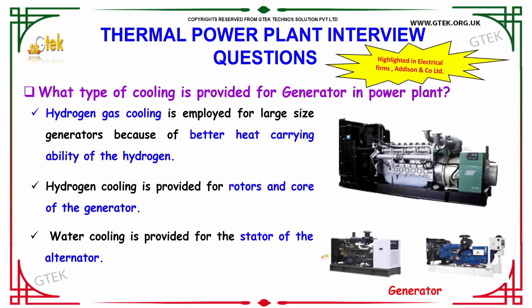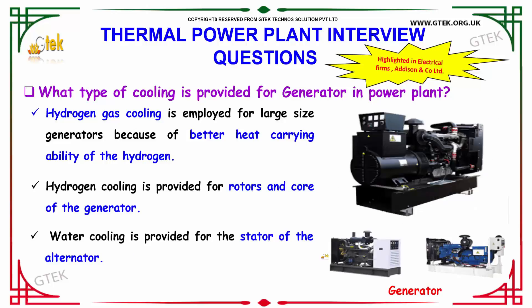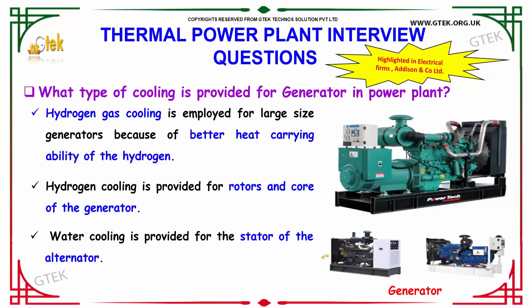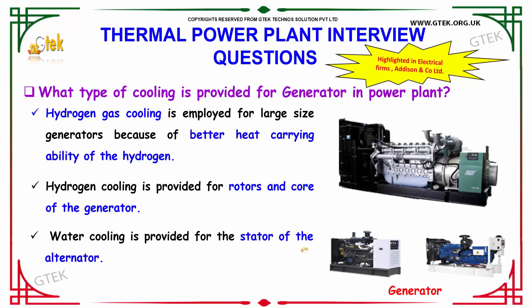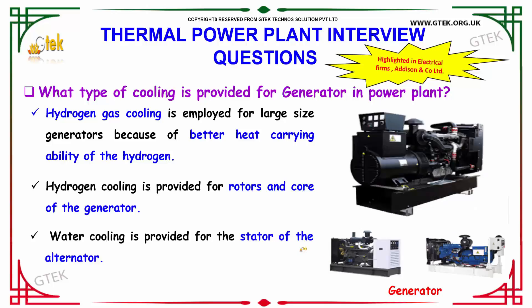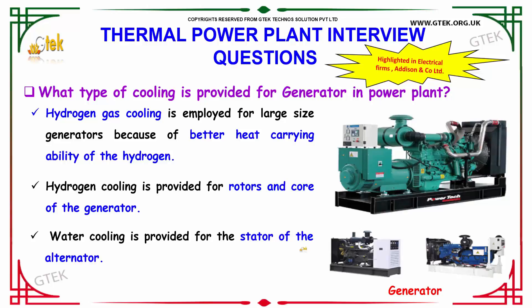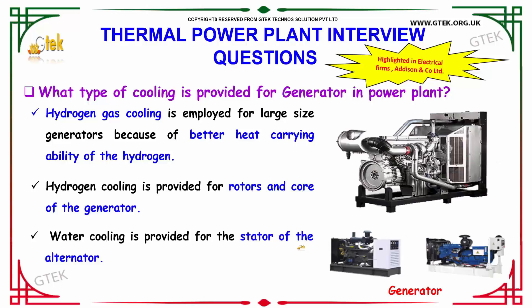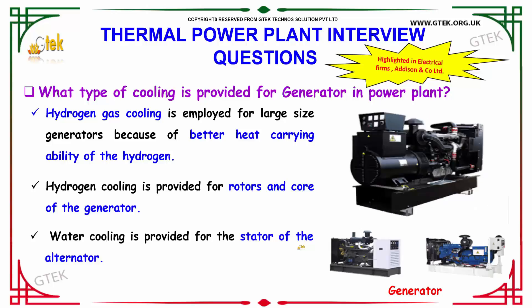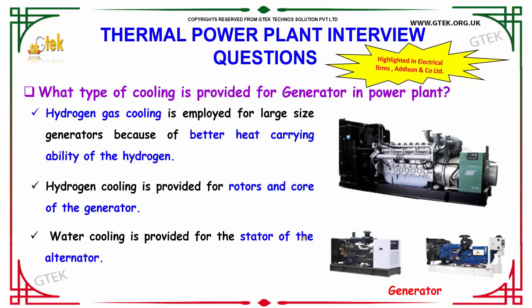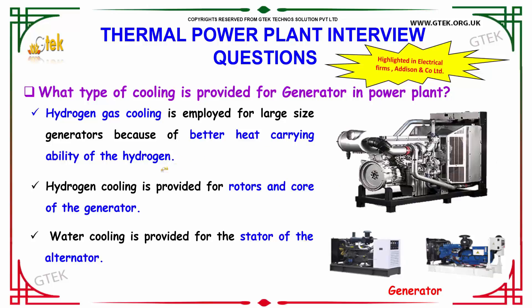What type of cooling is provided for generators in power plants? Hydrogen gas cooling is employed for large-size generators because of the better heat-carrying ability of hydrogen. Hydrogen cooling is provided for the rotor and core of the generator, while water cooling is provided for the stator of the alternator.